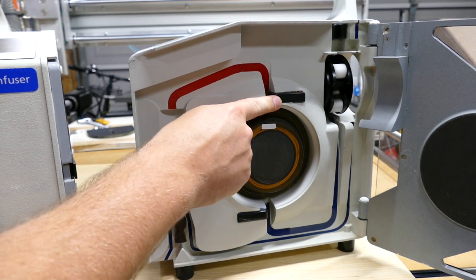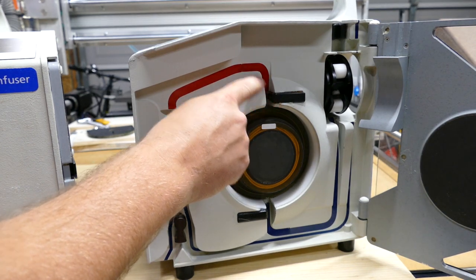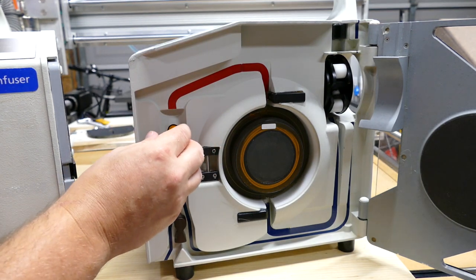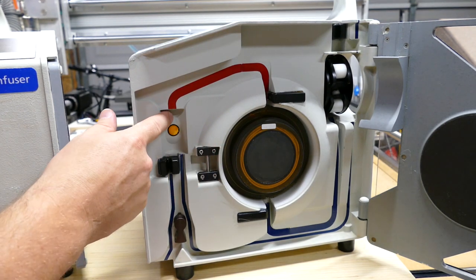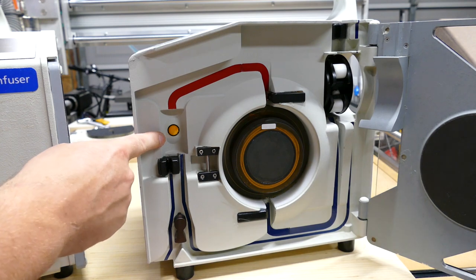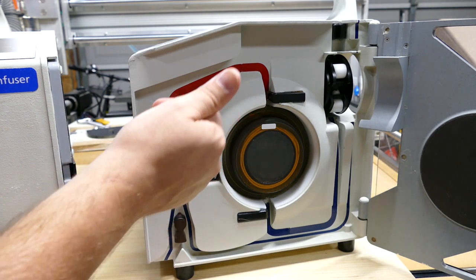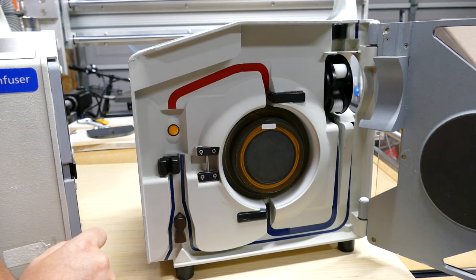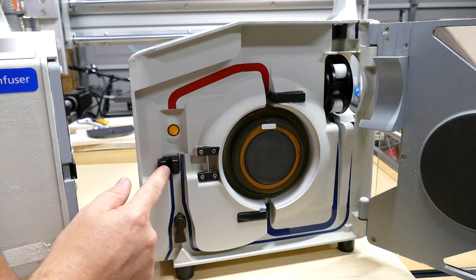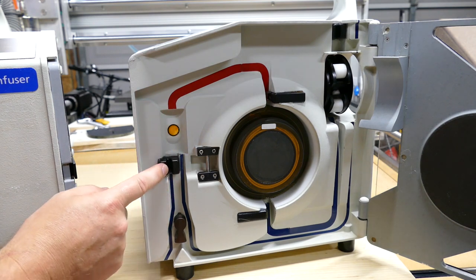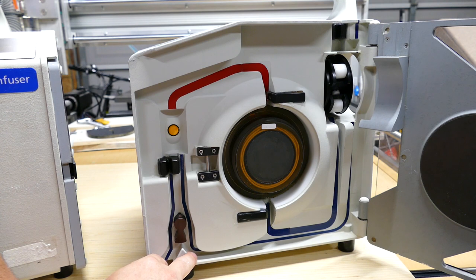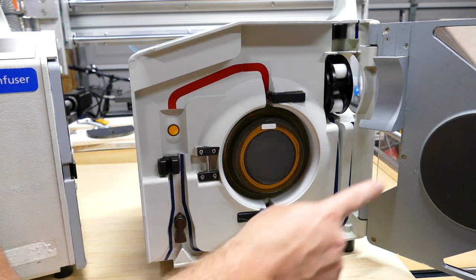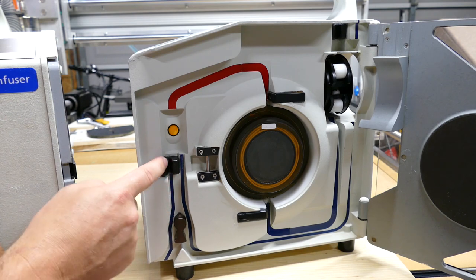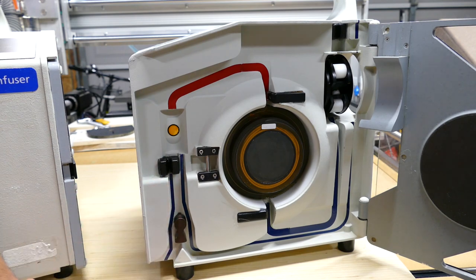This is also an infrared detector. It comes down here where your reservoir will press tightly up against this pressure sensor so it can detect both fluid out and whether there's an occlusion. Then the line will run down here and it goes through a bubble detect sensor and across this pinch valve. The pinch valve determines if the fluid is going to recirculate back around for prime or if it's going to exit out to the patient.